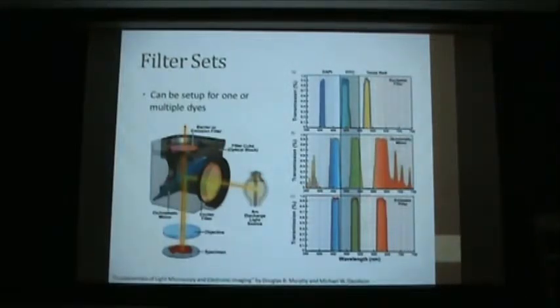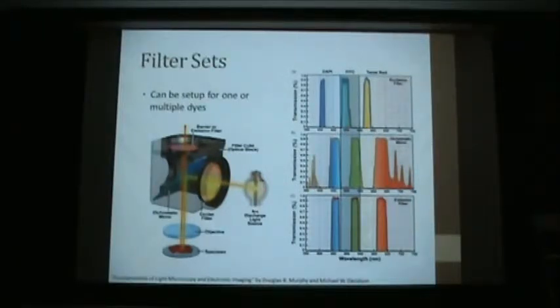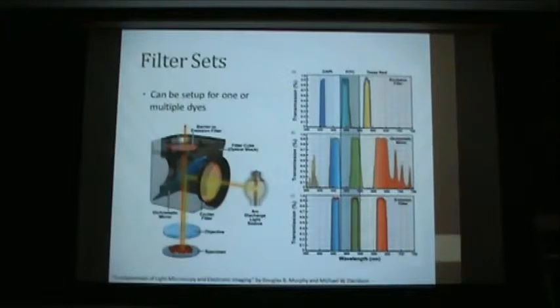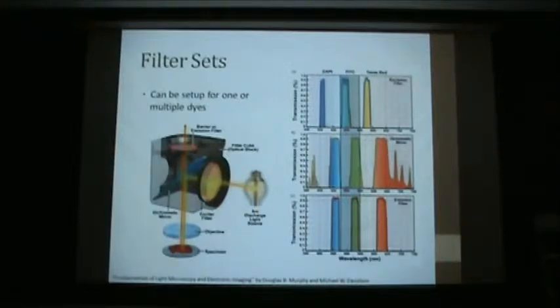These filters often go in a filter cube. Here we have a mercury lamp; it goes into an exciter filter which picks out the color we need to excite the dye. It's reflected off a dichroic mirror — dichroic means two colors in Greek; it reflects one color and transmits a different color. So here it will reflect the green light down to excite the specimen, and the red emitted light comes back up through the dichroic mirror. Then the emission filter cleans up any remaining excitation light. You can get filter cubes for a single color or for three or four colors at once.